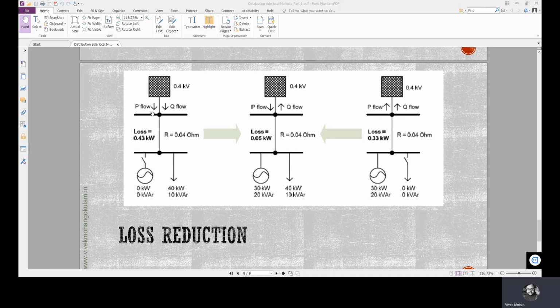In the first figure, we have both active and reactive power flow in the same direction, that is towards the local node from the upstream grid. Now the loss is 0.43 kilowatts, and the local generator is not connected. So the total load demand is completely fed from the upstream grid. Active power demand is fed from the upstream grid.